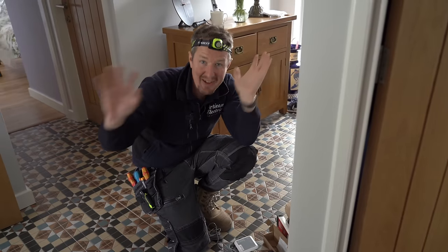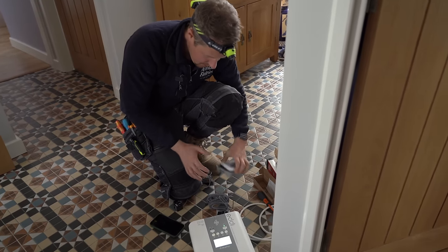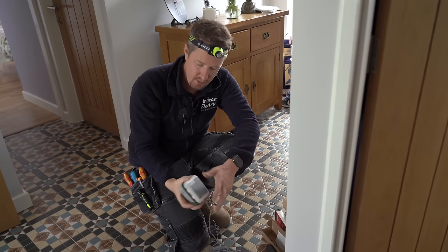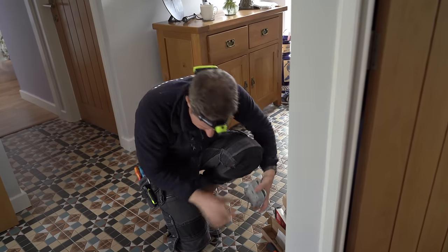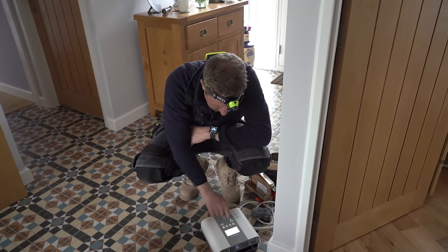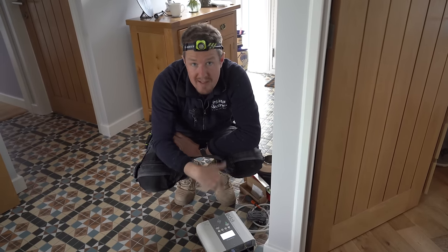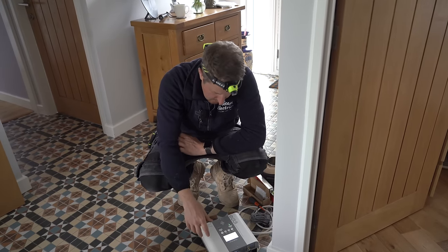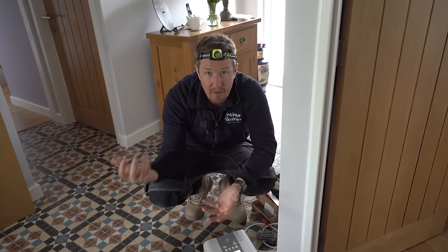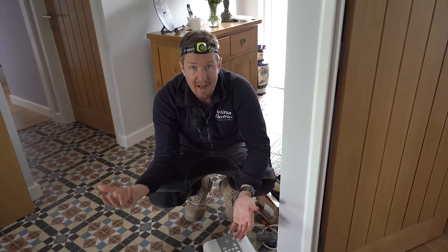We're connected to the internet and the customer's account is set up and paired with the device on their phones. Now we need to add the Harvi. Because it's self-powered from the CT clamp, we go to the meter box and clamp the CT around the cable to power it up, then pair it with the Eddi. CT1 is set as the grid CT — monitoring how much power the house is importing or exporting. CT2 is set for generation and battery, since they have a combined inverter and battery system, telling us how much power is coming from the solar and battery.